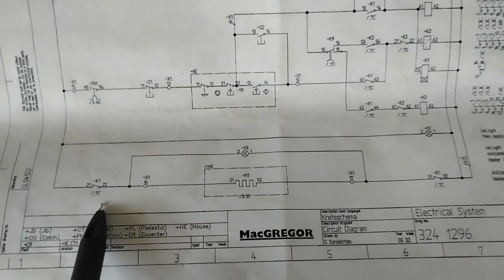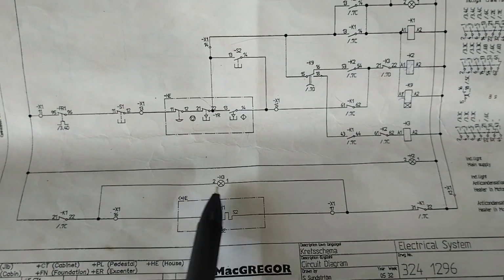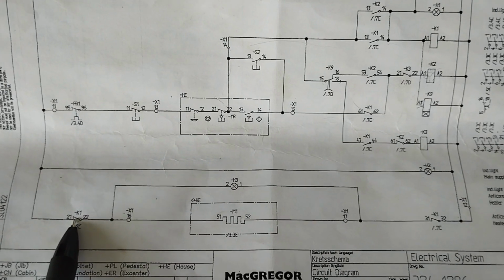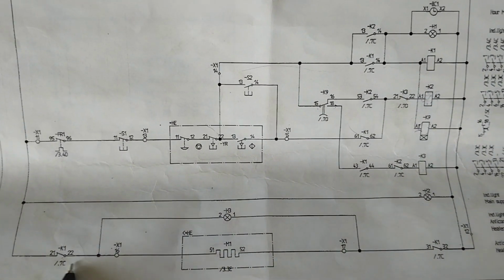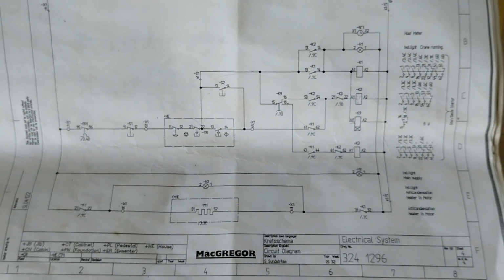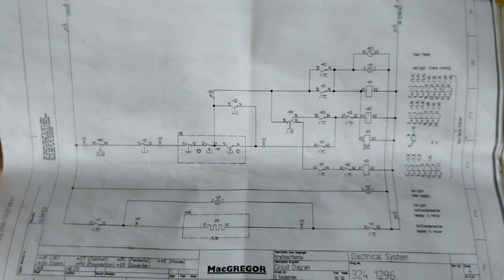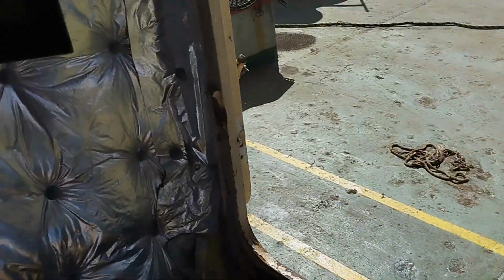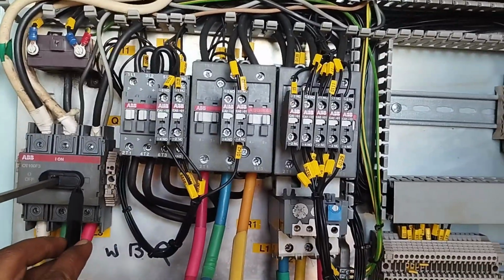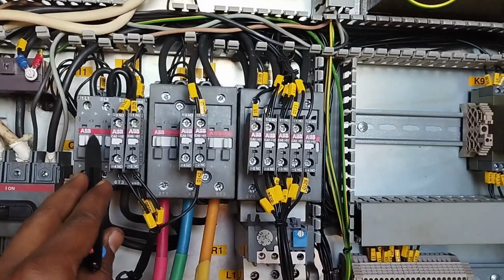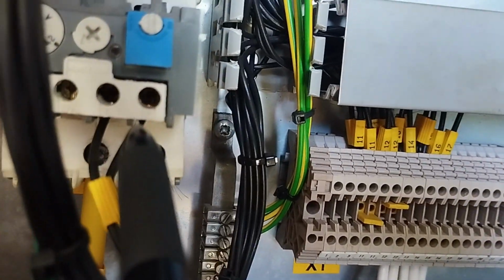Okay, so basically this is the heater for the motor. When contactor K1, the main contactor, energizes, this contact will open and the motor heater will turn off. Okay, so this is the control circuit for the provision crane or the lifeboat crane. Very simple. Now I will just explain the basic idea about the drawing. This is the main circuit breaker, this is the CT, this is the star contactor, this is the main contactor, this is the OLR, and most important in the OLR is 95 and 96.